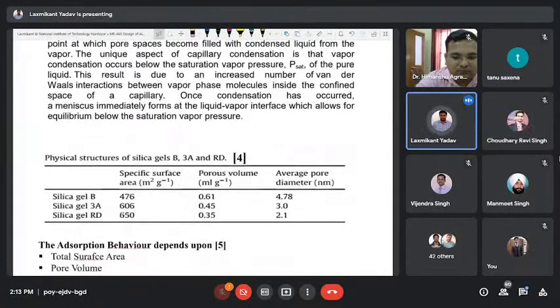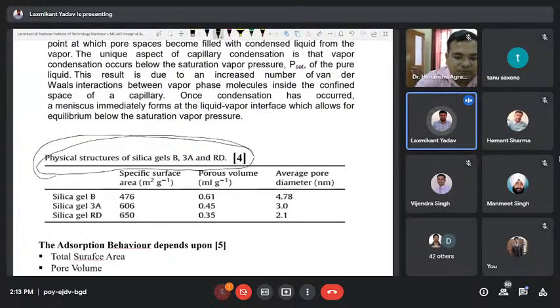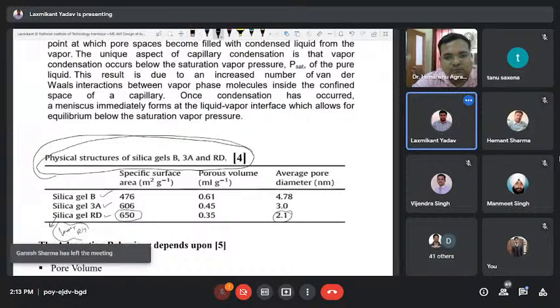Now the physical structures of silica gel. This physical structure is very important from the adsorption point of view, because it governs the isotherm curve. The isotherm is the graph of adsorption capacity versus relative humidity. You can see there are three types of silica gel: B, 3A, and RD. We observe that silica gel RD has a higher specific area but lower pore diameter, so silica gel RD will perform effectively at lower RH. In a lower RH environment, silica gel RD, the regular density silica gel, will perform effectively.